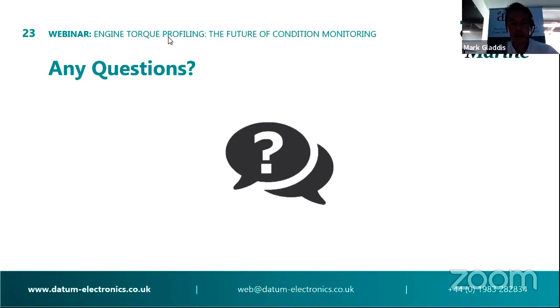We've done a lot of study into sampling and high sample rates. For things like gearbox meshing in the automotive industry, we go up to speeds of 20,000 samples a second. What we've realized from extensive testing in the marine industry is there's not a lot to be seen above 2 kilohertz frequency in the main shaft line itself. So currently the system will monitor at 2,000 samples a second.